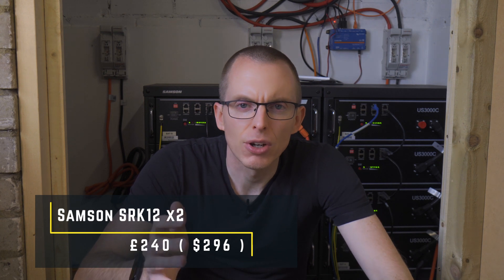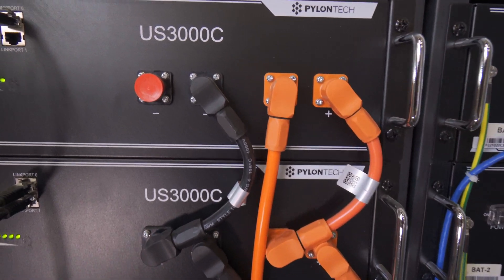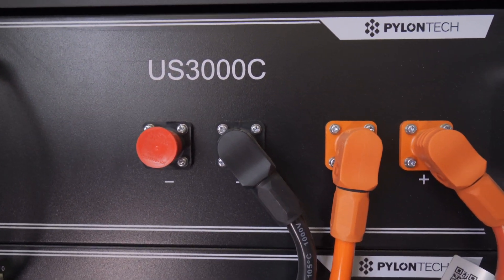To mount the batteries, I've probably made a mistake. I opted for Samson SRK12 rack mount cases at £120 each. A potential problem is that having four US3000C batteries in each case doesn't leave an air gap between the batteries for cooling, and could potentially cause problems in hotter weather. Currently internal battery temp peaks at 26 degrees when charging, so it's not causing a problem. I think I might look at welding together my own rack so I can still fit 12 batteries into this confined space.